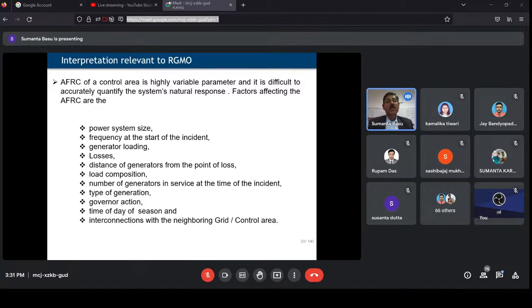It depends on the power system size, the frequency at the start of the incident, generator loading, losses, distance of the generators from the point of loss, load composition, number of generators in service at the time of the incident, type of generation, governor actions, time of day and season, and interconnections with the neighboring grid or control area. So you can understand that it is very complicated to determine all of these in practice. So it is monitored on a real-time basis, and it has to be calculated on a real-time basis to find out what the AFRC is at this moment.